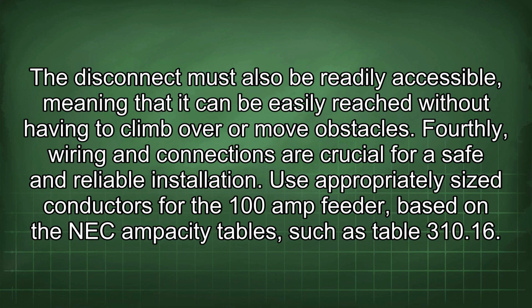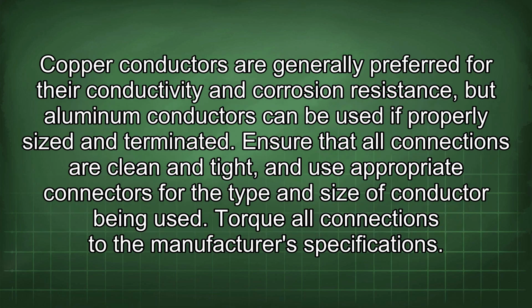Fourthly, wiring and connections are crucial for a safe and reliable installation. Use appropriately sized conductors for the 100 amp feeder based on the NEC ampacity tables such as Table 310.16. Copper conductors are generally preferred for their conductivity and corrosion resistance, but aluminum conductors can be used if properly sized and terminated. Ensure that all connections are clean and tight, and use appropriate connectors for the type and size of conductor being used. Torque all connections to the manufacturer's specifications.